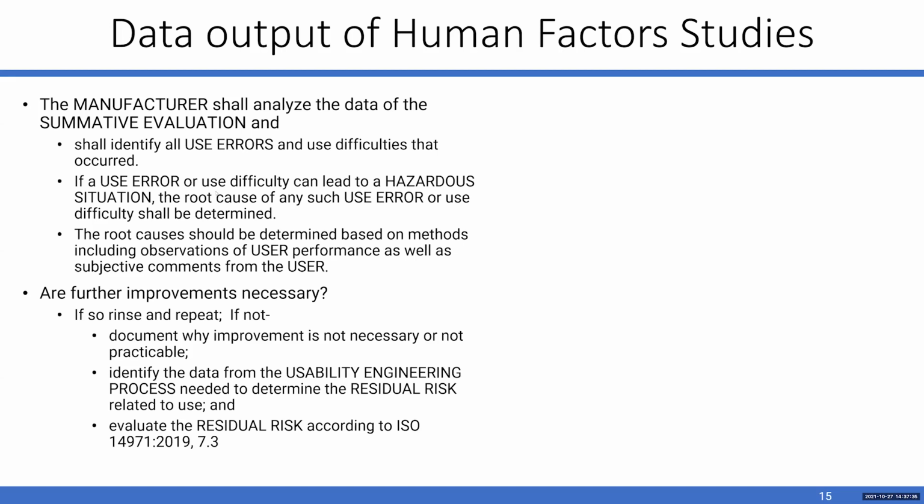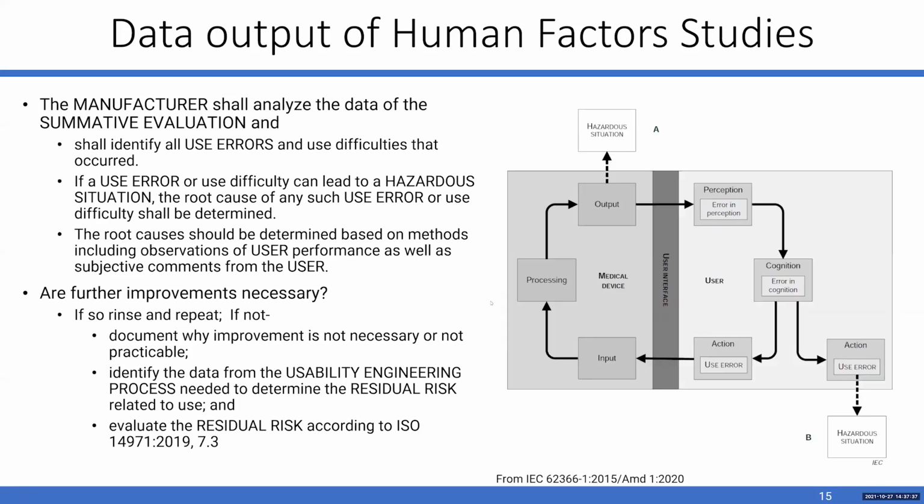So I know, coming from a quality background, a verification-heavy background, sometimes that's difficult, because in verification studies, you're very used to running statistical levels of evaluation, or again, process and accept on 7, reject on 8, the very numeric pass-fail type criteria. This is not that. This is an in-depth, deliberate, risk-focused analysis.